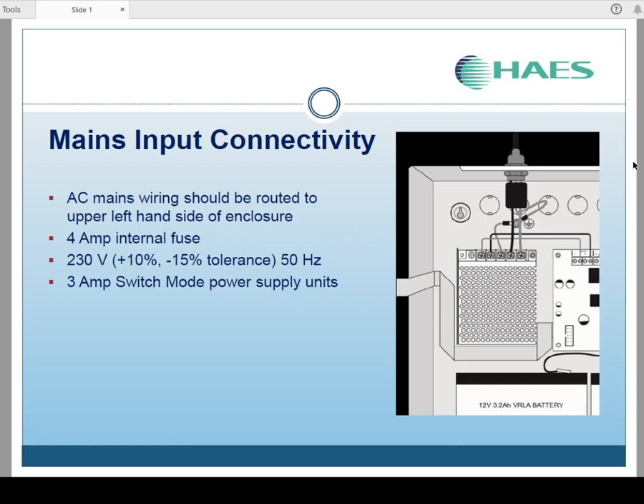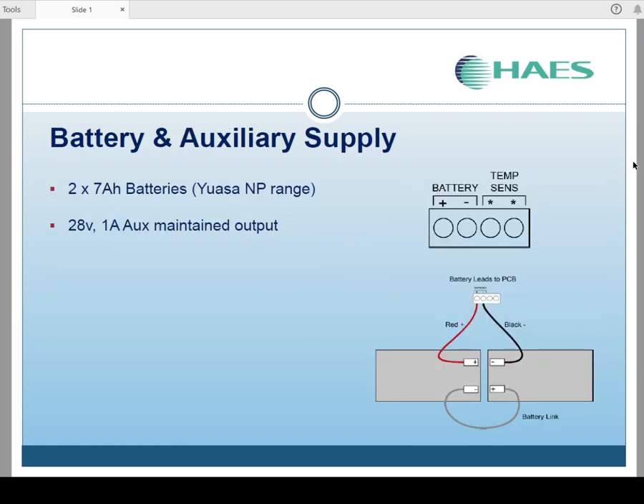For mains input connectivity, the AC mains wiring should be routed as far as possible to the upper left-hand side of the enclosure, so you're not running the mains cable all around the panel. The little PSU itself is equipped with a 4 amp internal fuse. It's non-changeable, it is electronic, so there's no reason for that to blow. The PSU itself is rated at 230 volts plus 10%, minus 10% tolerance at 50 Hertz, and it's rated at 3 amps continuous. The panel takes two standard 7 amp hour batteries.